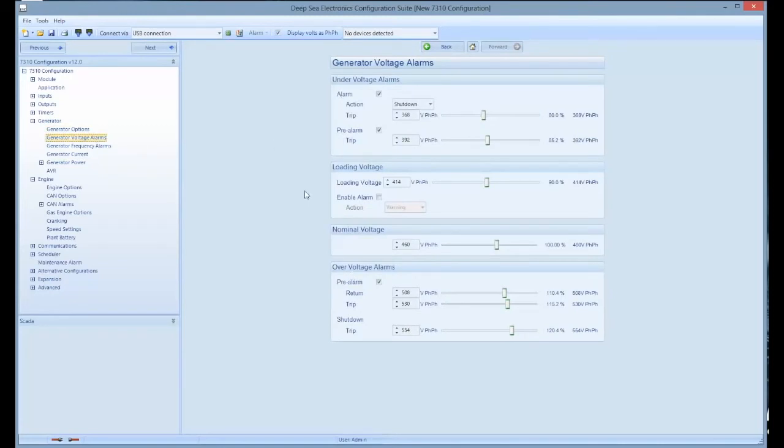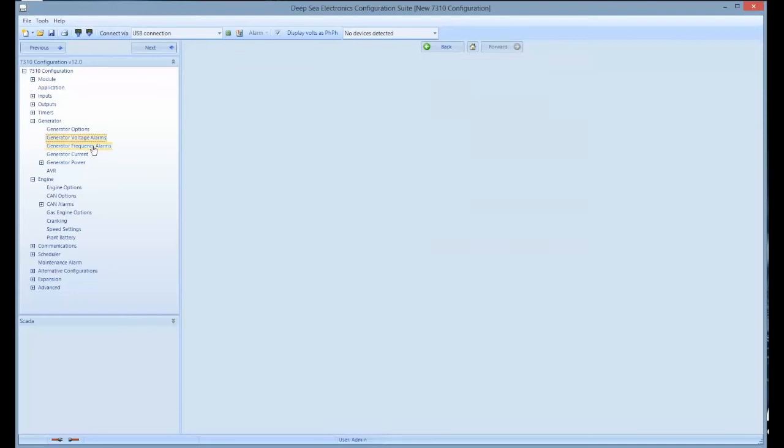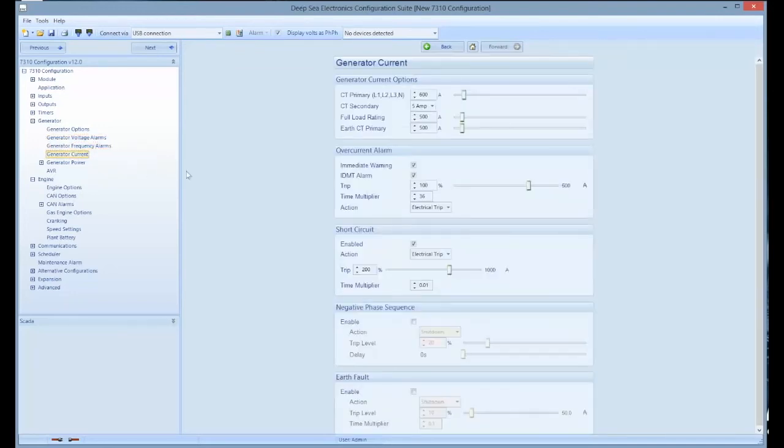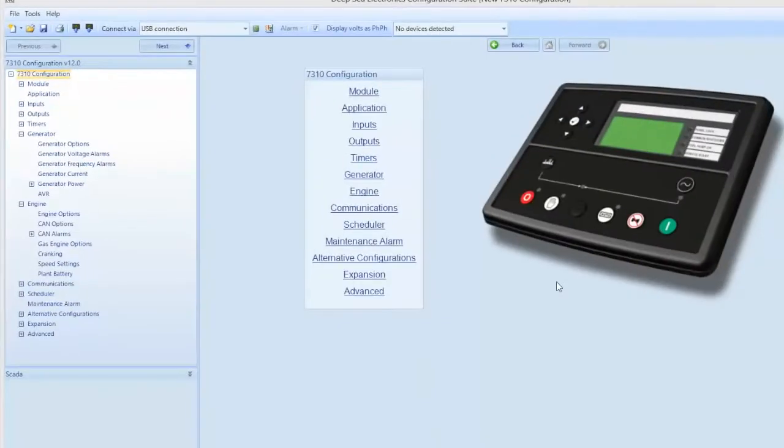By clicking on generator frequency, you can change your frequency alarm. And by clicking on generator current, you can change your amperage current alarm. As shown on the left hand menu, you have the capability of up to three alternative configurations.